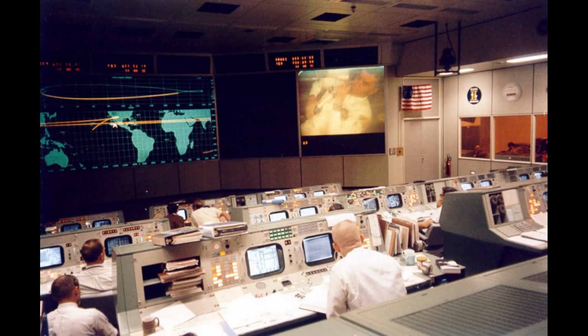Flight EECOM, and the O2 flow is right now pegged full scale high, although it's been varying. Go ahead, EECOM. We need to make sure the inline heaters for fuel cells 1 and 3 are off. 1.1, up to full scale high. The T-scan is about 445, and the condenser exhaust 180.